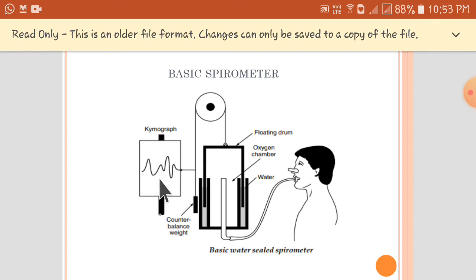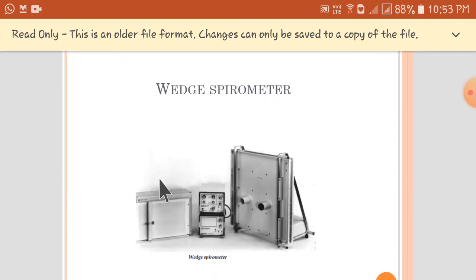Now, we are going to discuss the next one, that is a wedge spirometer. The wedge spirometer consists of two square pans, parallel to each other. They will be hinged along one edge. Hinged means attached at one end. One of the square pans is attached to a stand. It is permanently fixed, and it consists of inlet tubes. The other pan swings freely. The space between the two pans is sealed airtight, and it consists of bellows.